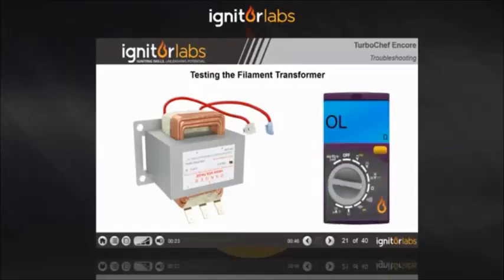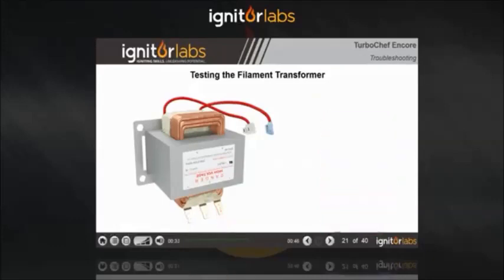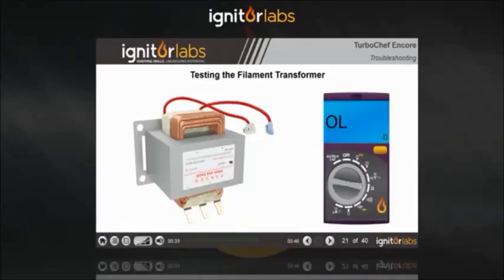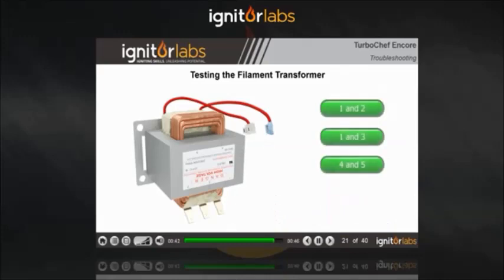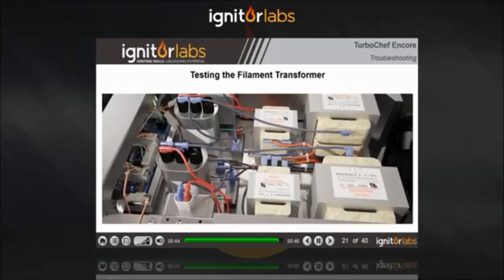With your meter on the ohm scale, measure between 1 and 3. You should see between 20.61 and 25.19 ohms. With your meter on the ohm scale, measure between 4 and 5. You should see very low resistance. If you see an open circuit, the transformer is bad.